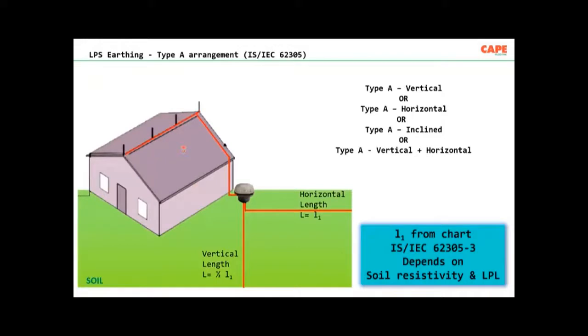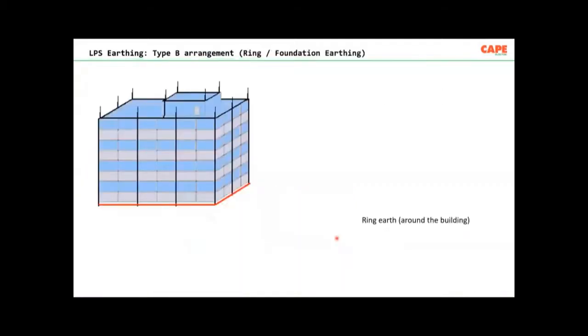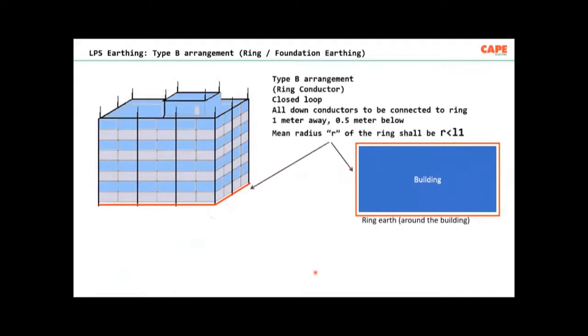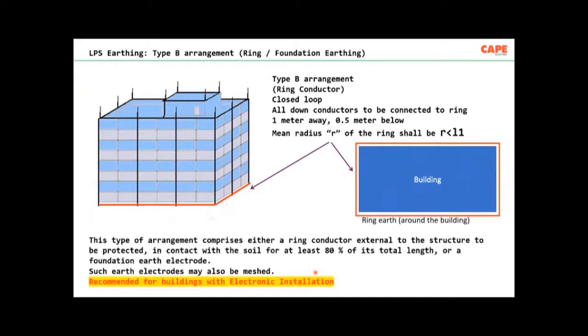Type A means every down conductor, you have to have either a vertical conductor or a horizontal conductor. This is called type A. Type A is recommended for smaller buildings. For larger buildings and larger industrial installations, we are supposed to have a ring conductor. Type B means a ring conductor all around the building, 1 meter away from the building, half meter below soil, as a closed loop. This is the best way of dissipating lightning current in existing buildings.